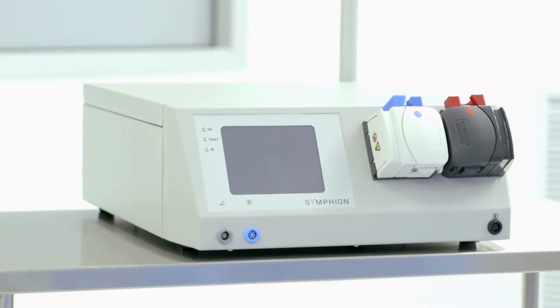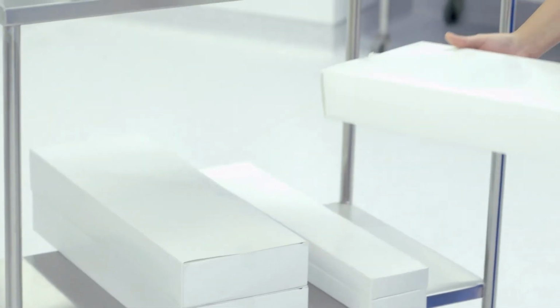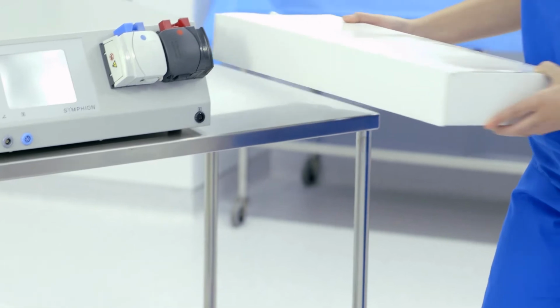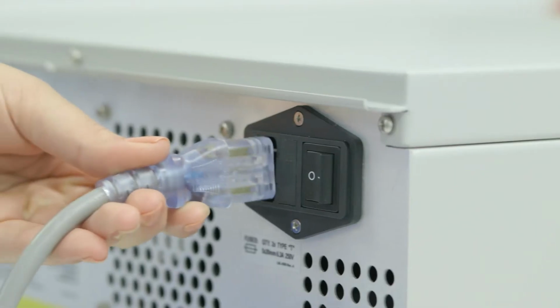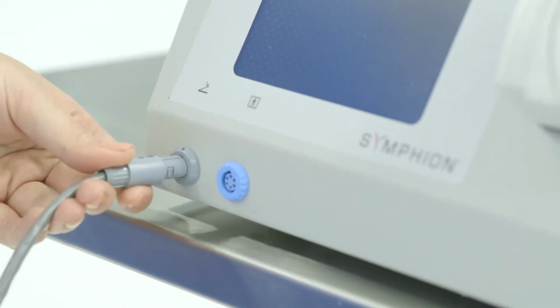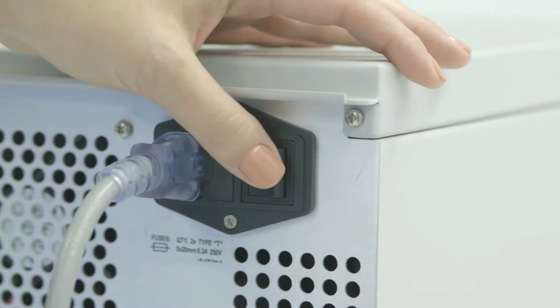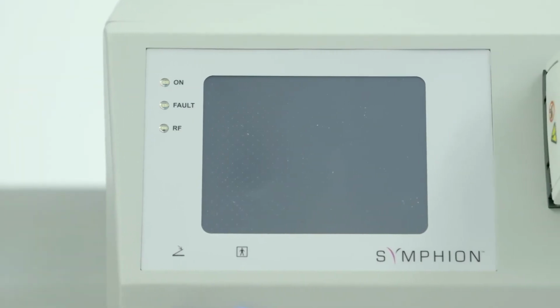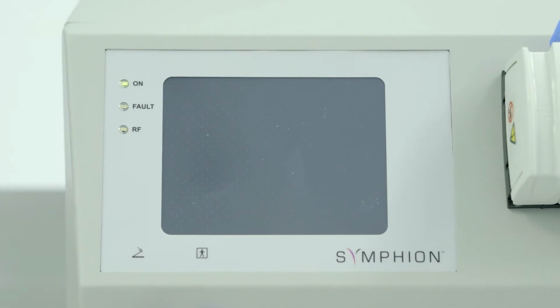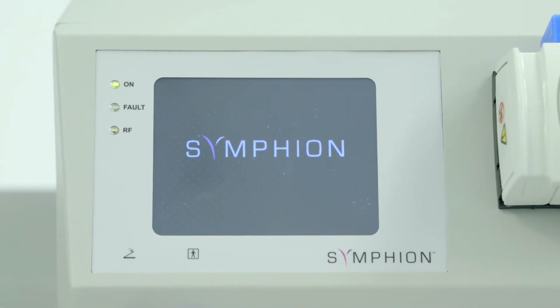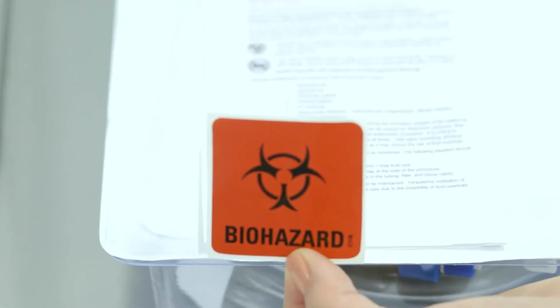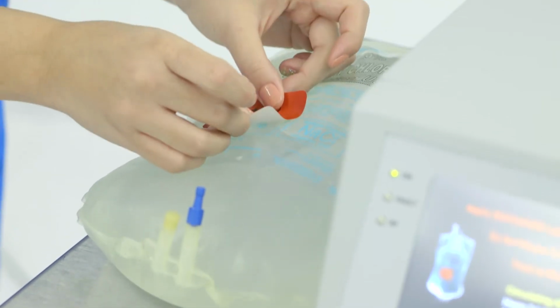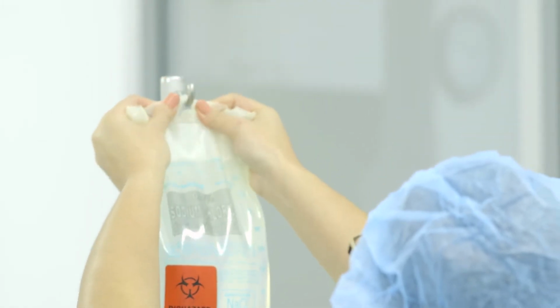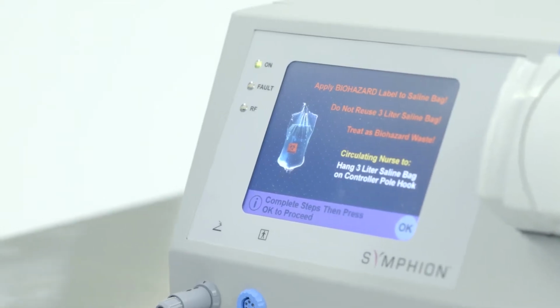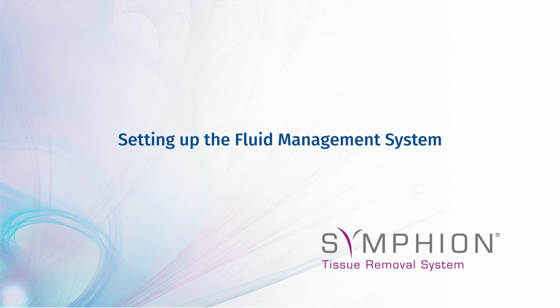Place the controller on a secure surface with sufficient space next to it for the disposable fluid management accessory tray. Connect the power cord and the foot switch cable to the controller and turn it on. Remember to always follow the instructions on the controller screen before proceeding. Apply the biohazard sticker found in the fluid management box to a 3-liter irrigation saline bag and hang it on the hook of the saline pole. Press OK on the controller display to proceed.